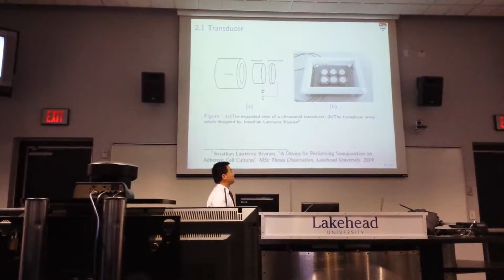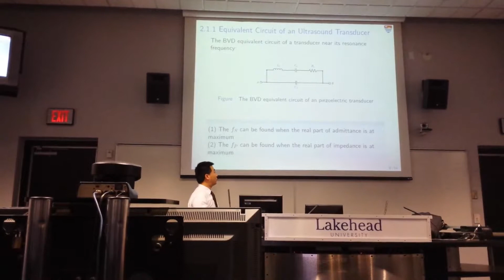Before we drive the transducer, we must know the characteristics of the transducer. This circuit is the equivalent circuit of a transducer. This is a combination of a parallel capacitance and a series resonant branch. So if we plot the transducer over a certain frequency range, we can get a series resonant frequency and a parallel resonant frequency. The series resonant frequency can be found when the real part of its admittance is at maximum. And the parallel frequency can be found when the real part of impedance is at its maximum.